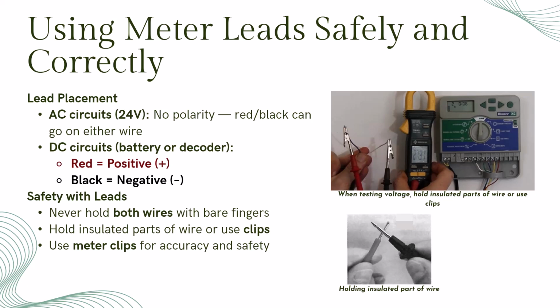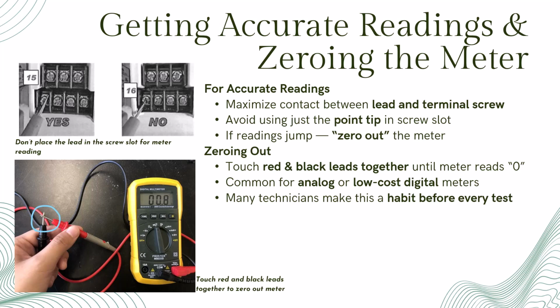And here's the safety part. Never hold both bare wires with your fingers when measuring voltage. Even 24 volts can give you a nasty shock under the right conditions. Instead, hold the insulated portion of the wire, or better yet, use meter clips for a stable hands-free connection. Even when your settings are correct, you can still get unreliable readings if the lead placement isn't right. When testing at a controller terminal, maximize the surface contact by placing the side of the lead against the screw head, not just the tip in the slot. Minimal contact can cause your readings to flicker or jump.